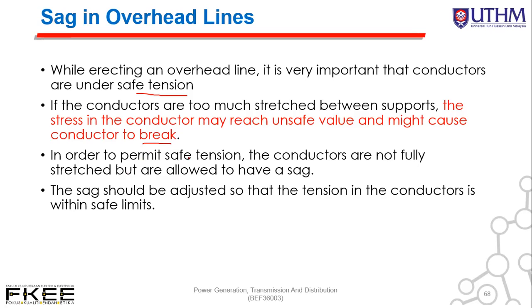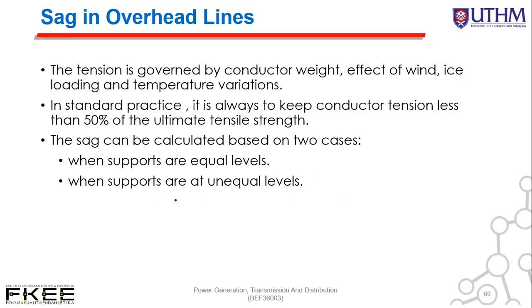Okay, in order to permit safe tension, the conductors are not fully stretched but are allowed to have a sag. The sag should be adjusted so that the tension in the conductor is within the safe limits. Okay. The tension is governed by conductor weight, effect of wind, ice loading, dan juga temperature variation. Okay.